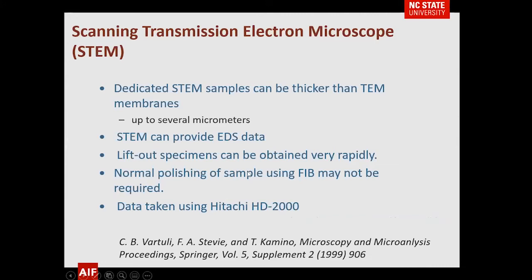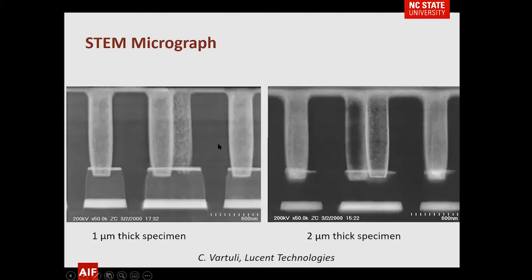It's also possible to use a scanning transmission electron microscope, STEM, which allows you to leave the sample thicker. This has advantages: in semiconductor work, as you're thinning, if you're not sure of the orientation you may remove more than desired. With STEM you can image a sample quite a bit thicker — these images are from a one-micrometer and a two-micrometer thick specimen. You can get some idea of the structure in three dimensions and determine where to thin and which side to thin further.